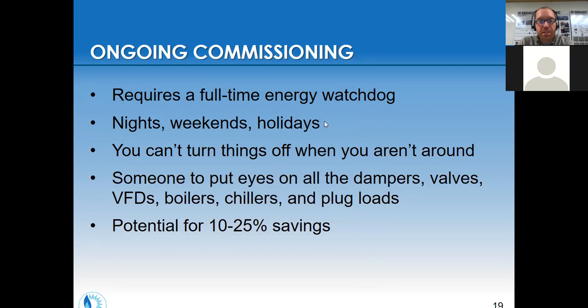Ongoing commissioning is something we'll just touch on briefly. This can require a full-time energy watchdog on nights, weekends, and holidays. It's really applicable to larger libraries that can bring on staff to turn things off during those times, or an occasional person who comes in during the later night hours and puts eyes on dampers, valves, VFDs, boilers, chillers, and plug loads.